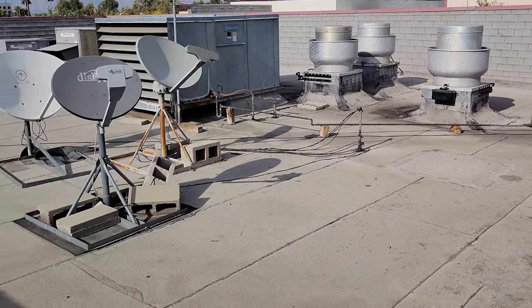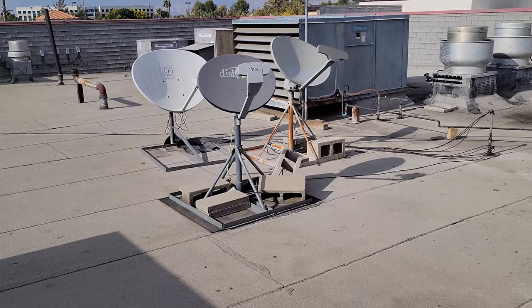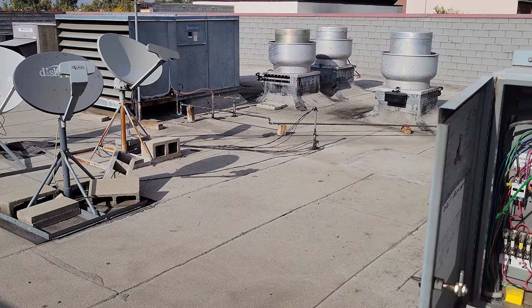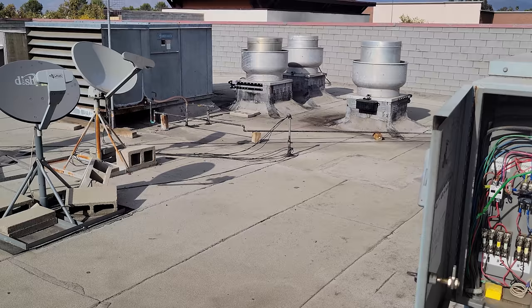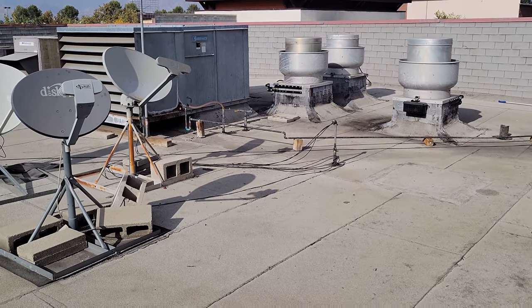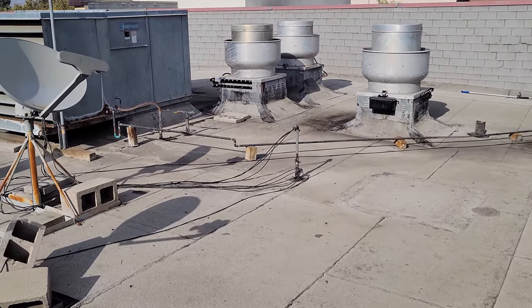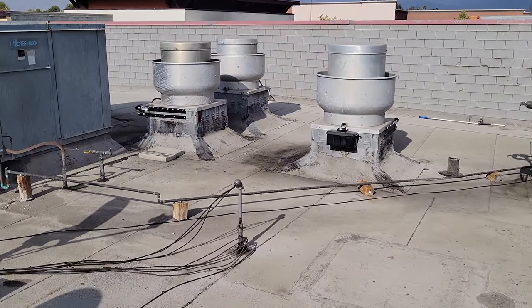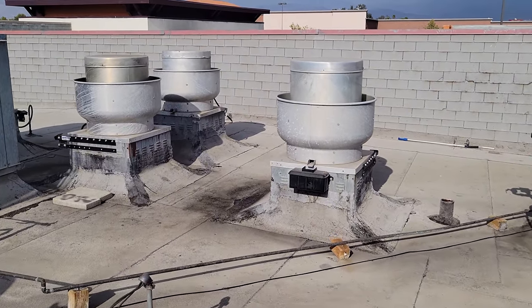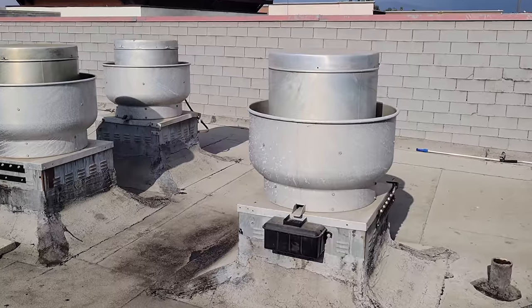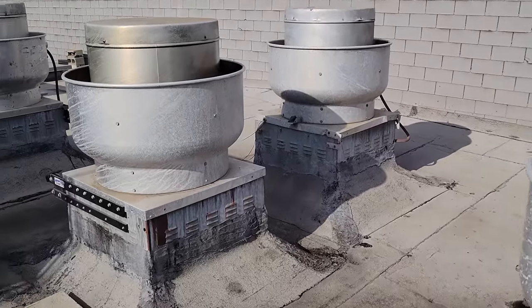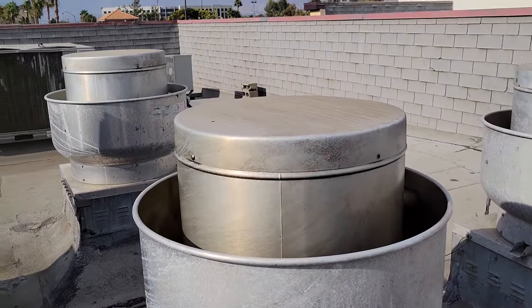But I know for a fact that all their fryers are down. All their cooking equipment's down and all their exhaust fans are down, which intrigues me because they do have a shunt on this system, and if like the Ansul system triggers or something like that, it'll kill everything in the line, but it typically shouldn't kill the exhaust fans. The exhaust fan should still be powered. So that's very interesting. What is going on here?